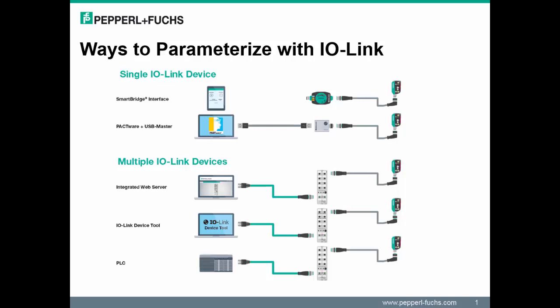In this launch, we introduced three new ways to parameterize IO-Link devices: the integrated web server, the IO-Link device tool, and the PLC. With SmartBridge and USB Master, you are limited to parameterizing a single device. However, with the IO-Link Master and its ability to connect multiple IO-Link devices, you now have the ability to perform parameterization on multiple devices connected to the IO-Link Master.